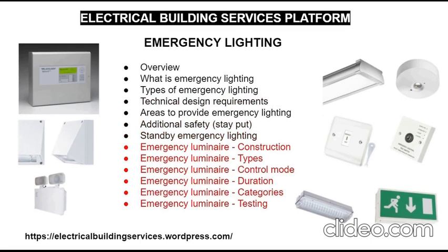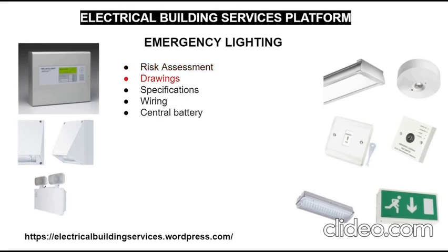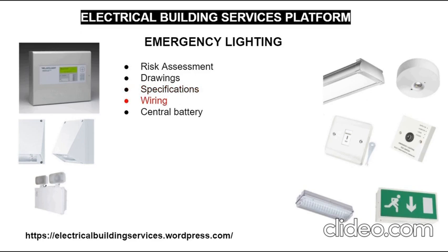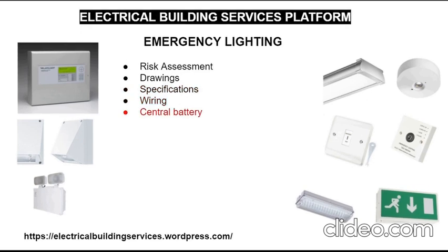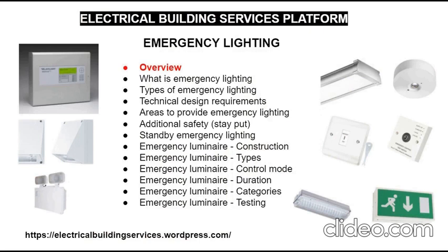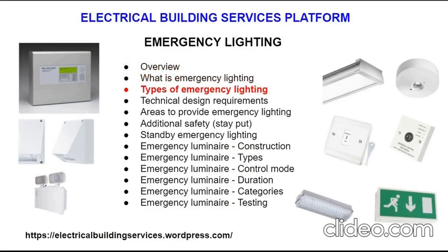Entertainment, including temporary, such as licensed premises, evening dance, even though you've got school, you need 3 hours. You also need to provide illuminated signage above the door. That is recommended. The emergency light should show the door and the threshold, so it must be within 2 meters of that door to provide proper illumination.